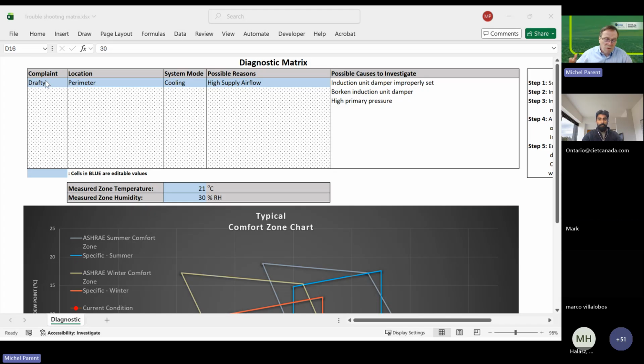So you will enter the type of complaint that you have, where it's located, either perimeter or interior, what the mode is, and then it will tell you the possible reason for this and the cause to investigate. You'll say, hey, it's likely this, or this. And it will do that for drafty, too hot, too cold, and it will allow you to kind of guide your investigation on that system.